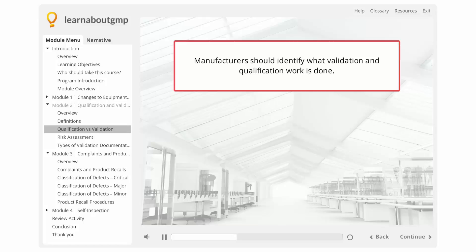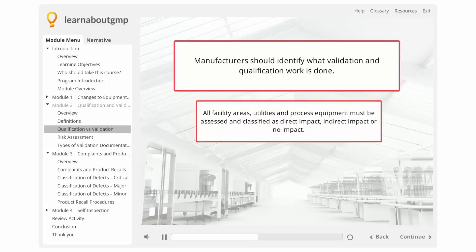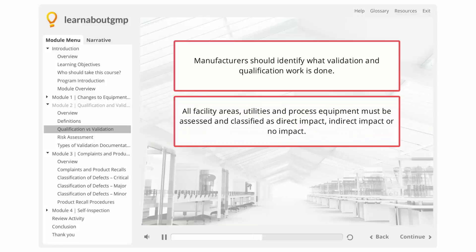Manufacturers should identify what validation and qualification work is done. All systems, equipment, processes, and procedures should be reviewed, and the manufacturer should decide what qualification and validation work needs to be performed. All facility areas, utilities, and process equipment must be assessed and classified as direct impact, indirect impact, or no impact.